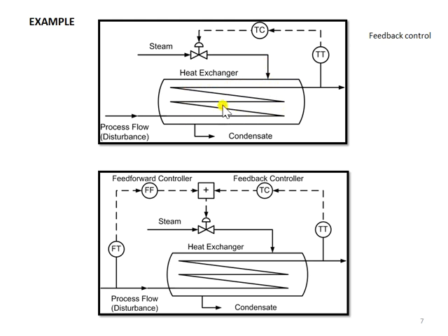This behavior of increasing and decreasing temperature will be monitored through the temperature transmitter, and the temperature transmitter will send the signal to the temperature controller, and the temperature controller will send the signal whether to open more or to reduce the steam valve.